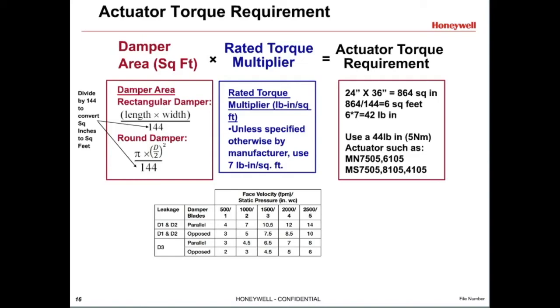So you should select a 44 inch-pound or 5 Newton-meter actuator such as the MN7505 or 6105 non-spring return, or MS7505 or 8105 spring return. To help simplify the math, this chart shows the maximum damper area for each actuator series based on the 7 inch-pound per square foot torque multiplier. Simply calculate the area of the damper in square feet, then look for the actuator torque needed. For example, if a damper has a 15 square foot area, then a 175 inch-pound actuator should be selected, such as a spring return modulating MS7520 or non-spring return 24 volt floating MN6120.